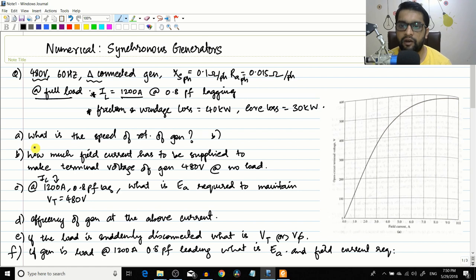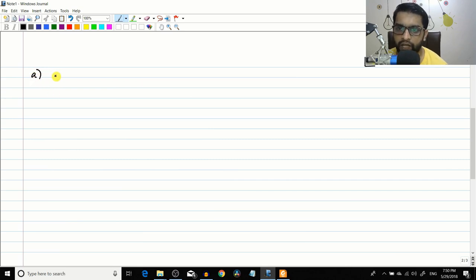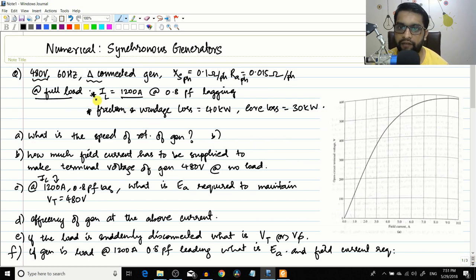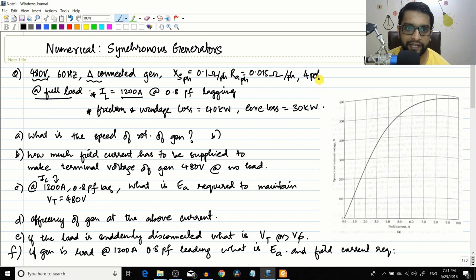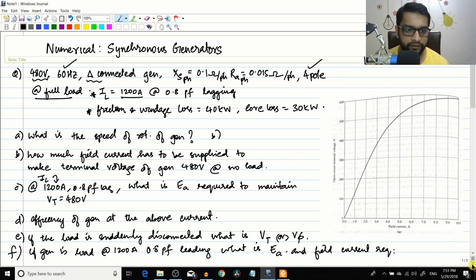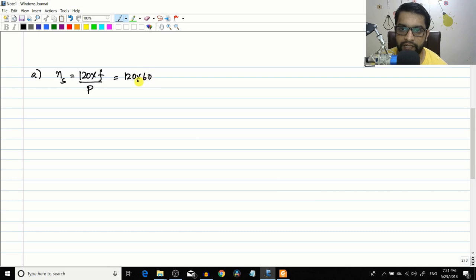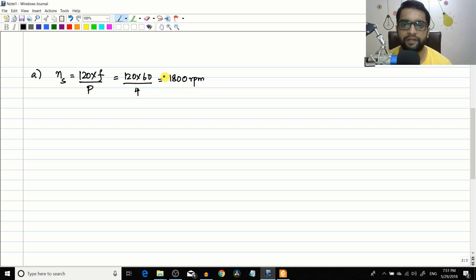The first question asks for the speed of rotation of the generator. The synchronous speed formula is Ns = 120f / P. The frequency is 60 Hz and it is a four-pole generator, so substituting: Ns = 120 × 60 / 4 = 1800 RPM. The first part is straightforward.